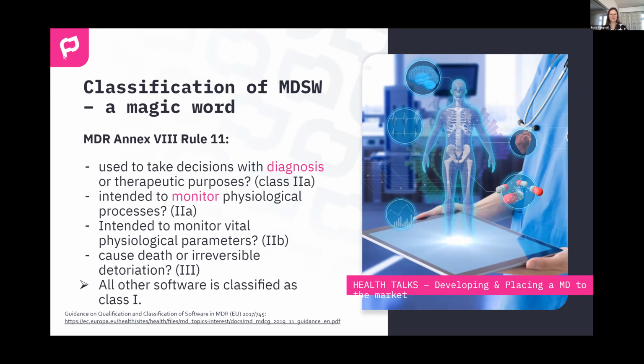The other magic word is monitoring. If your software is monitoring any physiological processes, it's 2A category. Monitoring vital physiological parameters, 2B, and then the most critical medical device software. If your software can in any way cause death or irreversible deterioration of the patient, it's class 3. Thus, the strictest requirements apply to your software. If you don't have any matching magic words, diagnosis, monitoring, then you might be able to get your software still in class 1 under the MDR.